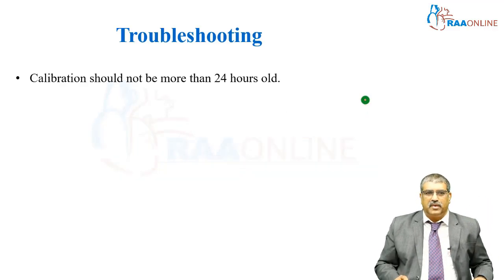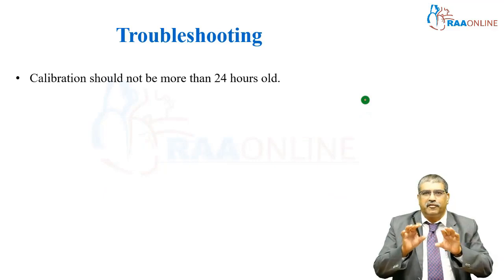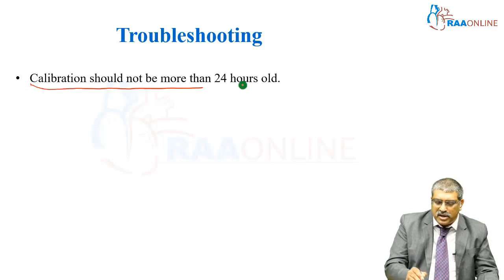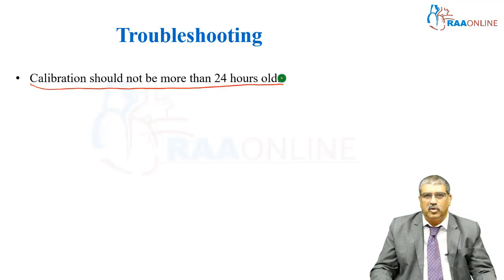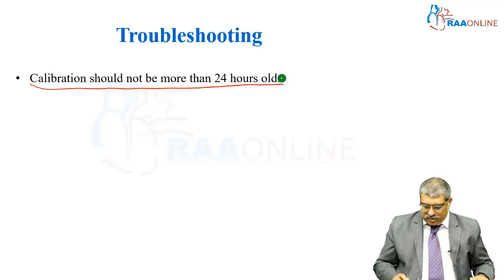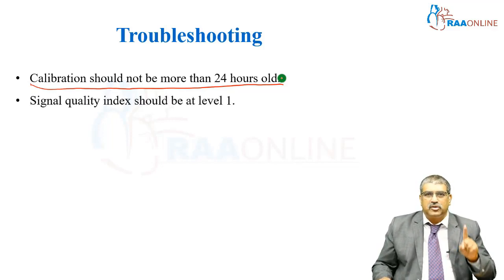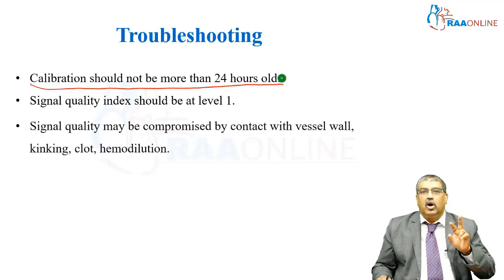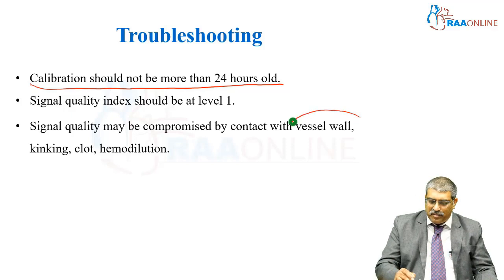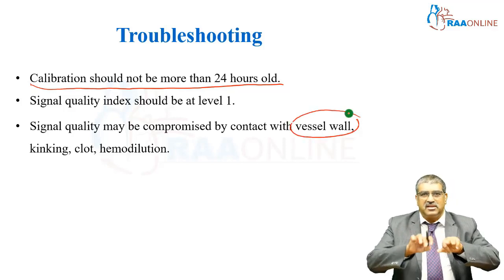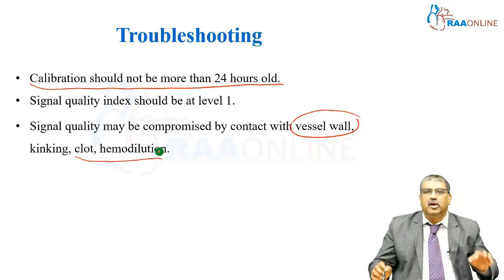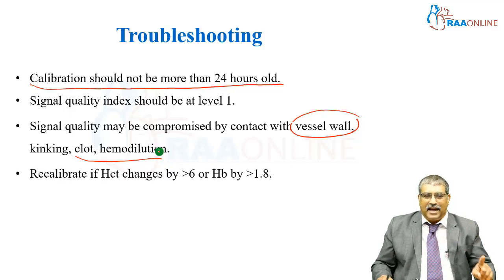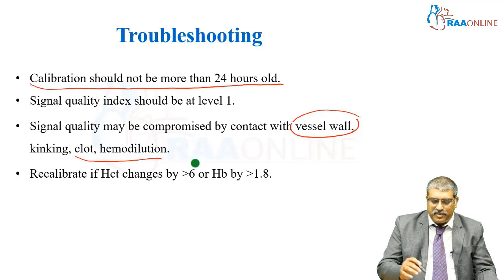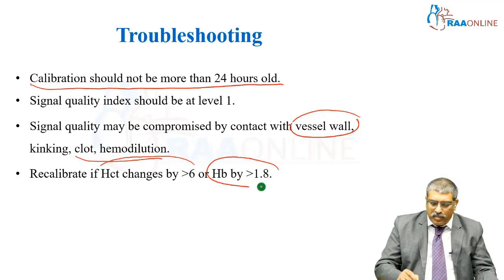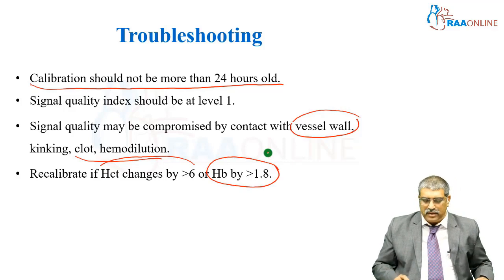And coming to a few salient points of mixed venous oxygen saturation, the calibration should not be more than 24 hours old. It should be calibrated every 6 to 8 hours. Signal quality index should be at the level of 1. Signal quality may be compromised if the PA catheter contacts the vessel wall, or there is a kinking in the PA catheter, or some clot or hemodilution happening inside the lumen of the pulmonary artery. Recalibrate if the hematocrit changes by 6% or the hemoglobin changes by greater than 2 gram per deciliter.